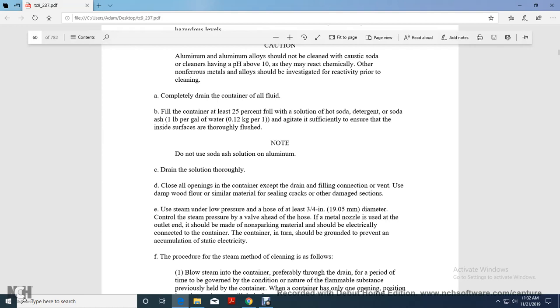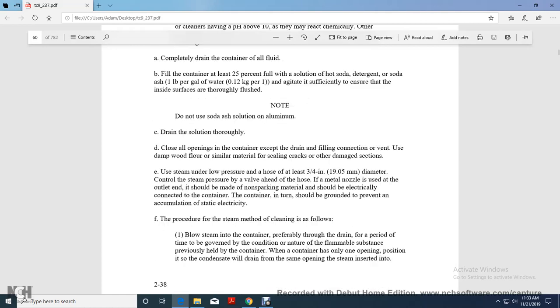Close openings of the container except for the drain and the filling connection or vent. Use damp wood flour or a similar material to seal cracks or other damaged sections. Use a steam hose under low pressure, at least 3/4 of an inch in diameter. Control steam pressure with a valve at the head of the hose. A metal nozzle at the outlet end, made of non-sparking material, should be electrically connected to the container. The container should be grounded to prevent accumulation of static electricity.